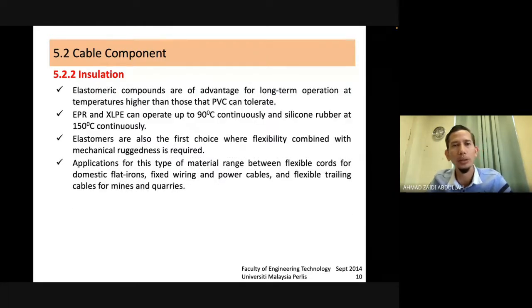And then it also elastomeric compound are advanced for long-term operation, temperature higher than those PVC can tolerate. Okay, for long term lah. So that's why you can see that the PVC cable, it can be used up to 15 years, 15 tahun. So under JKR standard, the wiring for all building of government, it was suggested to replace after 15 years. Selepas 15 tahun baru diminta buat wiring semula.